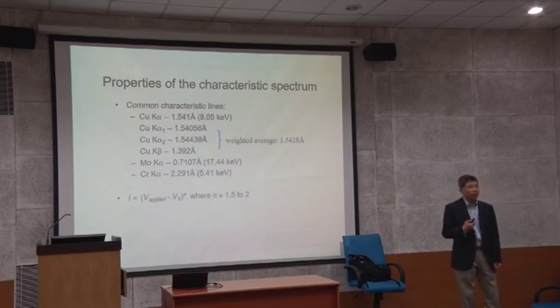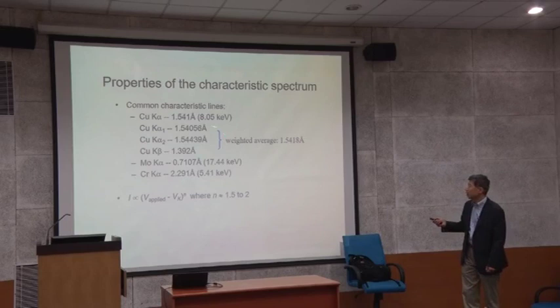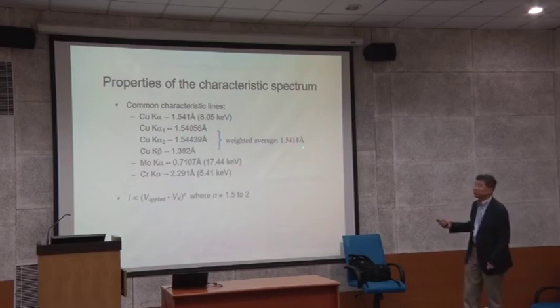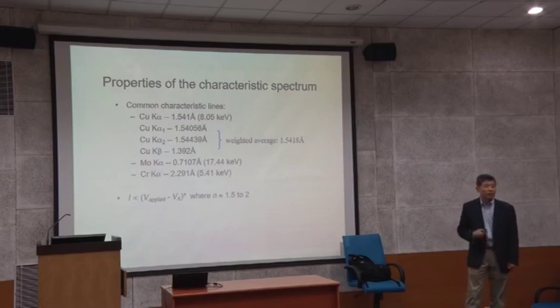If your source X-ray is monochromatic, a very clean K alpha 1, you have to use that wavelength to calculate all this d-spacing. And if you use a weighted average, where K alpha 1 and K alpha 2 are not separated, you have to use that wavelength to calculate it. So I think you have to understand what exactly your incoming X-ray source is.